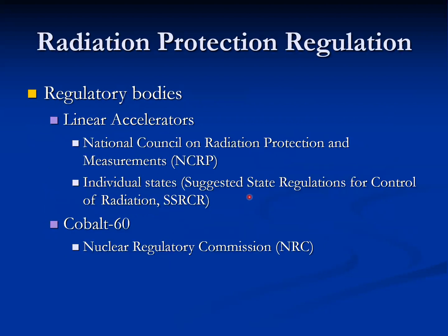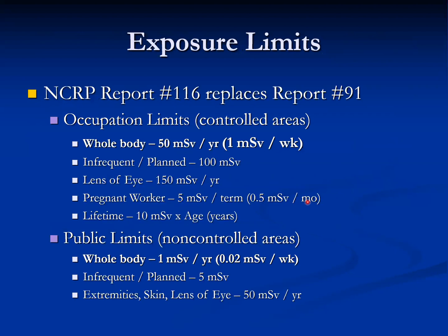Regarding radiation protection regulations, relevant regulatory bodies include those for linear accelerators, the National Council of Radiation Protection and Measurement (NCRP), individual states (SSRCR), and for Cobalt-60, the NRC. NCRP report 116 replaces report 91. Occupational limits and controlled area limits are defined, and one should be aware of these values in order to provide a safe environment.